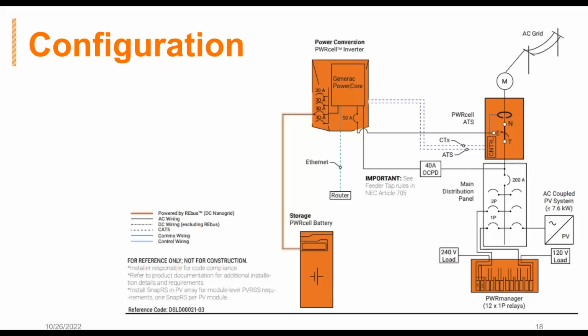Just note that you do need the transfer switch in order to do AC coupling. From a configuration perspective, here are all of those components: the battery, the inverter, the transfer switch, and the Power Manager. In order for us to turn the third-party PV on and off when the grid is down, it needs to be interconnected on the load side of the transfer switch. That way, when the grid goes down, our inverter simulates the grid, and the third-party PV inverter turns back on, thinking the grid has come back.